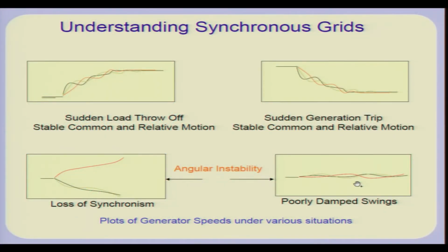Now, this change of voltage will be picked up by the automatic voltage regulator, which changes the field voltage of the generator. You will find that the field flux also starts oscillating, and because of that the torque also oscillates, and suppose this torque oscillation is such that it actually enhances the oscillation. Because of this feedback control system, at certain frequencies the damping of the oscillation may not work, and it may in fact feed into or enhance the oscillation. Incidentally, control systems in the power system can actually destabilize these power swings, and instead of dying out they may be poorly damped or even increase in magnitude.